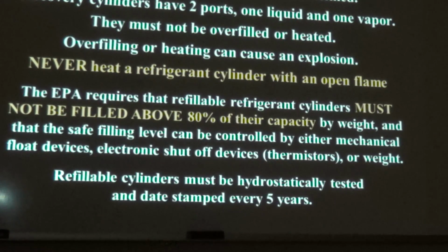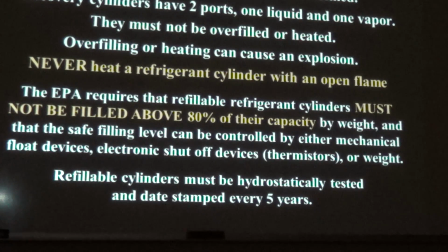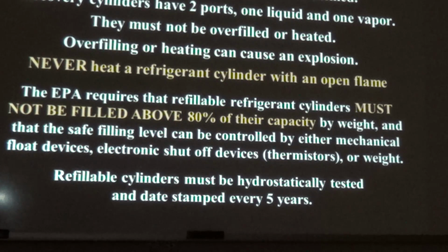Some things to be reminded about. 1, never heat a refrigerant cylinder with an open flame. The EPA requires that refillable cylinders must not be filled above 80%. So the key word here is the 80%. That's what they're looking for. If you see refillable cylinder, recovery cylinder, how much to put in there, it's never to exceed 80%. And the 80% is the answer on the test that you're going to look for.